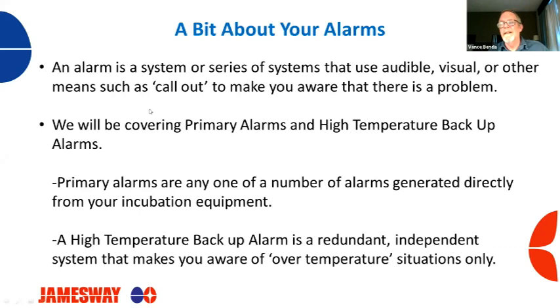We'll be covering primary alarms and high temperature backup alarms. Primary alarms are any one of a number of alarms that can be generated directly from your incubation equipment. Examples most people will be familiar with are high temperature, low temperature, high humidity, low humidity, and turning. There's a long list of things that can make your incubator send an alarm. High temperature backup alarms, on the other hand, are a redundant, independent system that makes you aware of over temperature situations only. As I said, your incubator already has a high temperature alarm, but this system is redundant, independent, and backs up your incubator. If something were to go wrong with a temperature probe or something on your incubator, this system is there to help catch a high temp situation before you do any damage to any embryo.